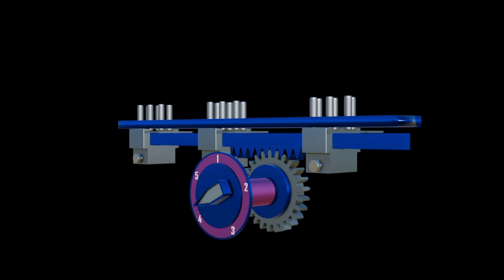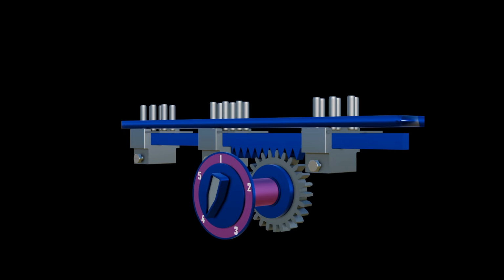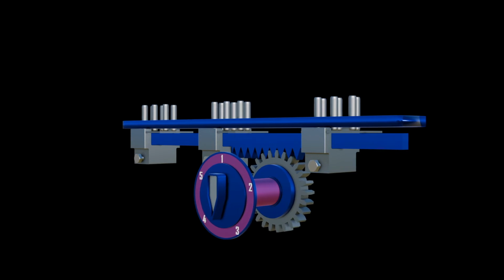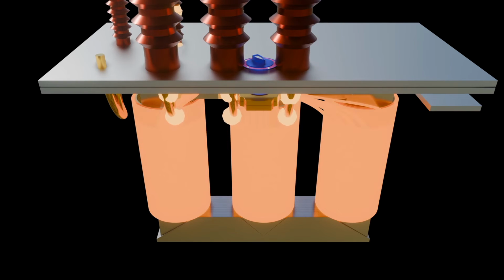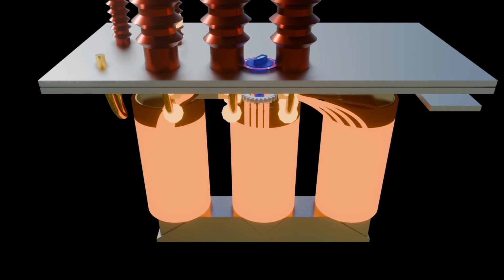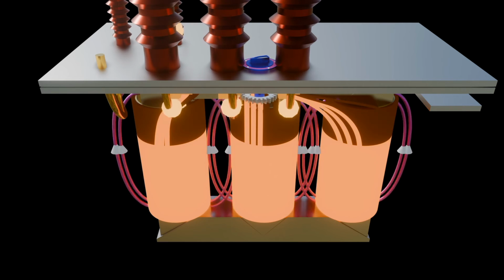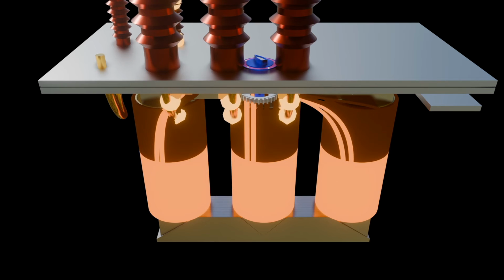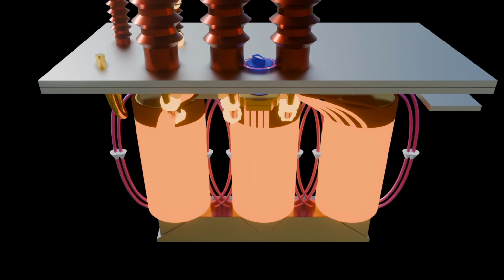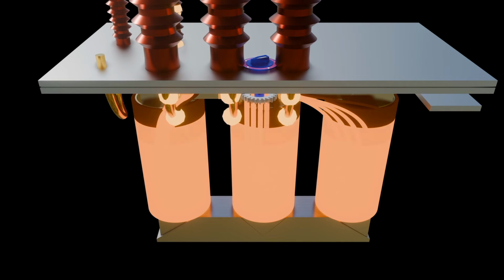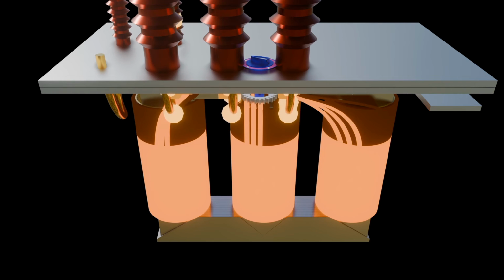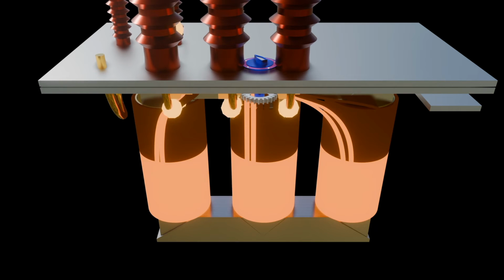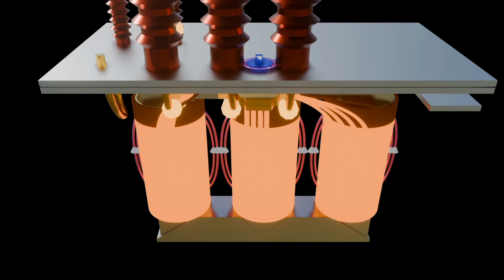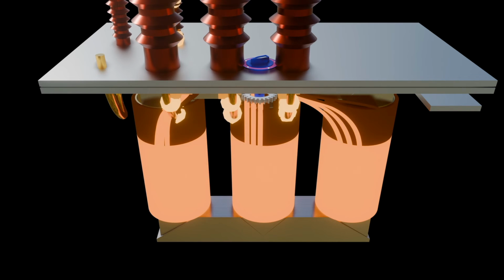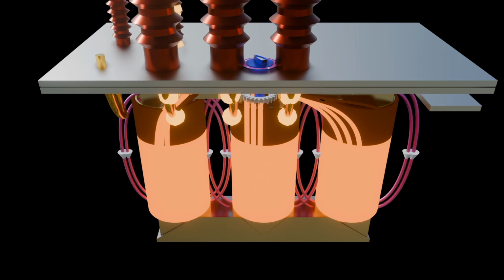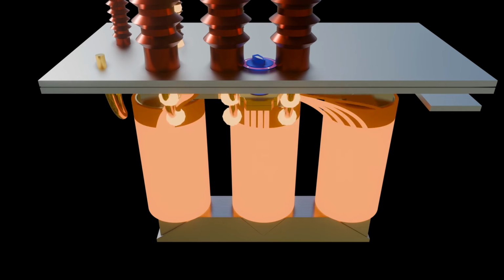Tap changers are provided at HV windings because of the following: the number of turns on the high voltage winding is large and hence a fine voltage variation can be obtained. Current on the low voltage winding of the transformer is high and hence interruption of high current is a difficult task. Also, the LV winding is placed nearer to the core and the HV winding is placed outside. Therefore, providing taps on the HV winding is comparatively easier than if we provide the taps on the LV.